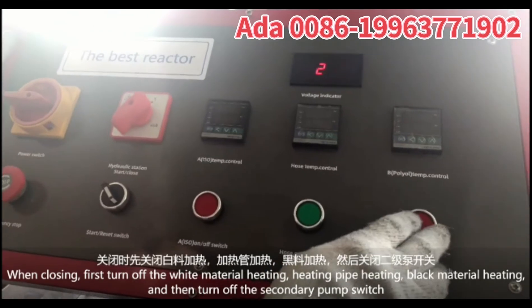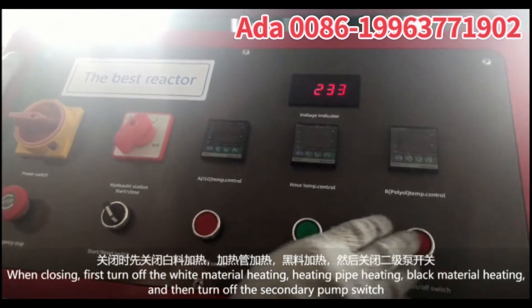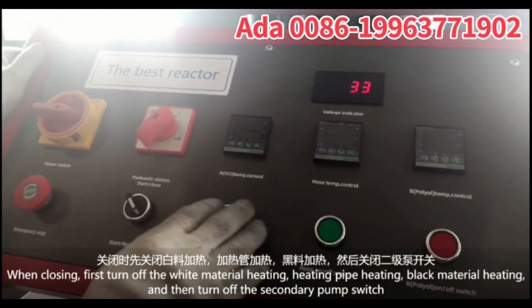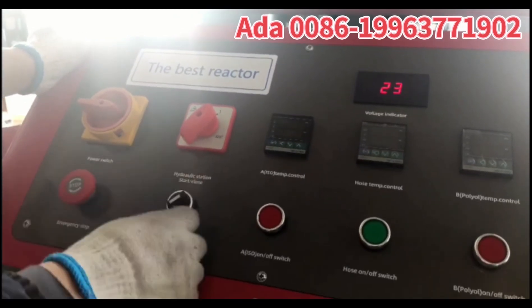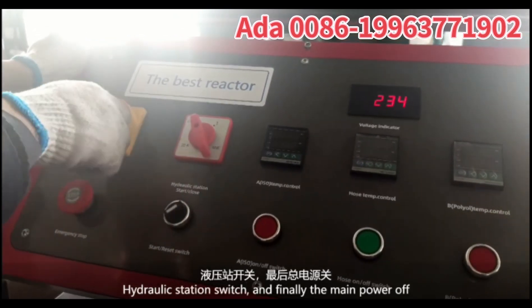When closing down, first turn off the white material heating, then the heating pipe heating, then the black material heating, and turn off the secondary pump switch, then the hydraulic station switch, and finally turn off the main power.